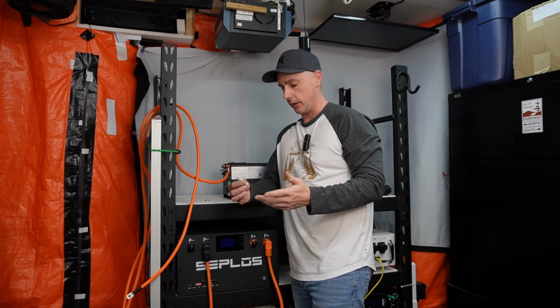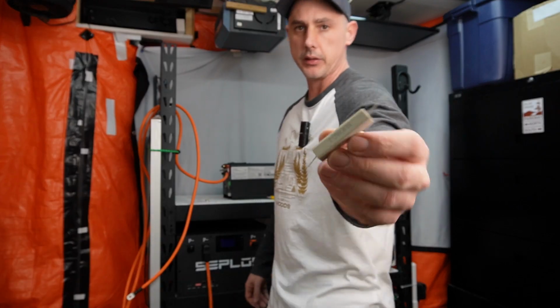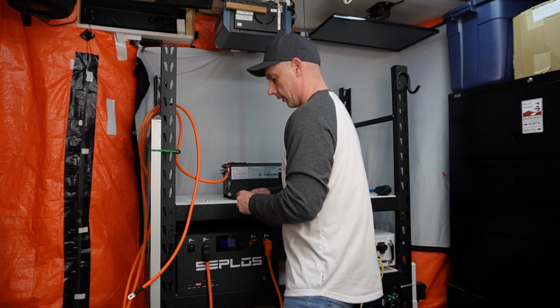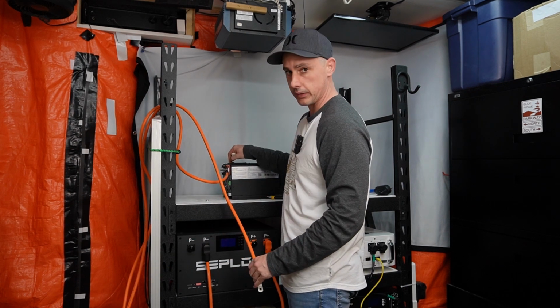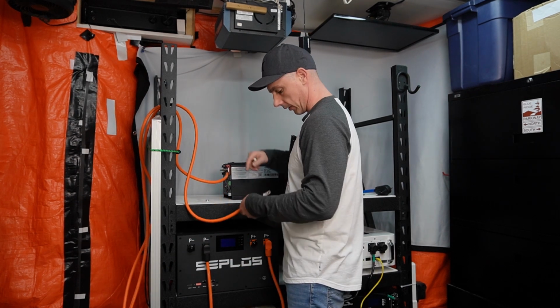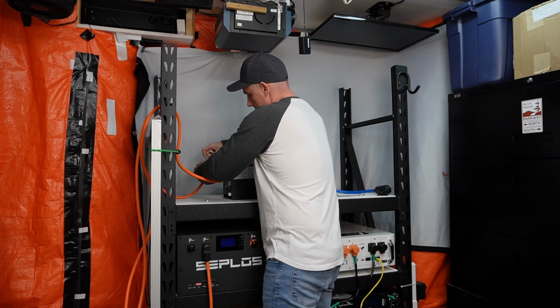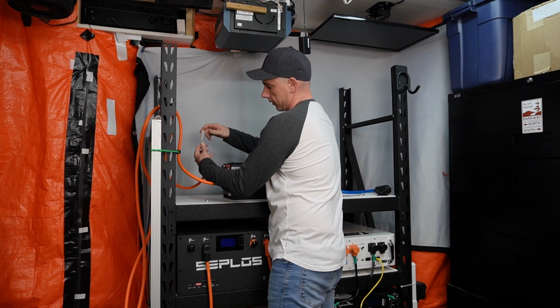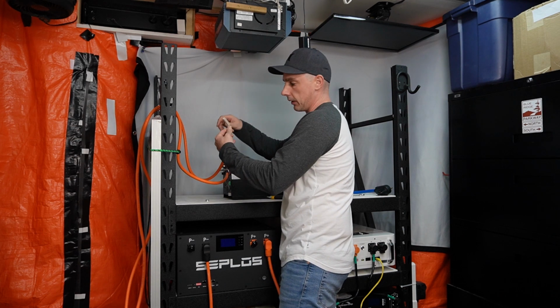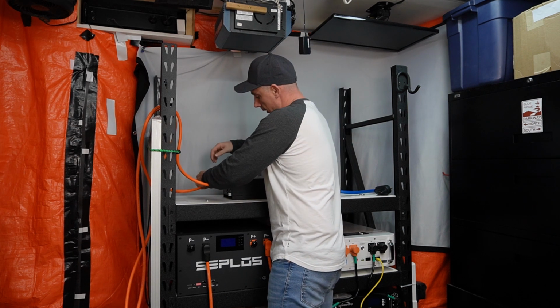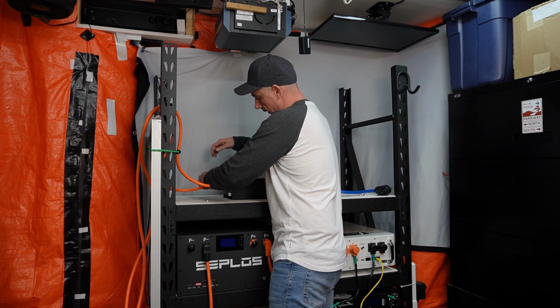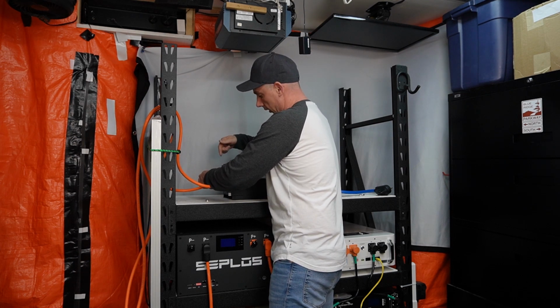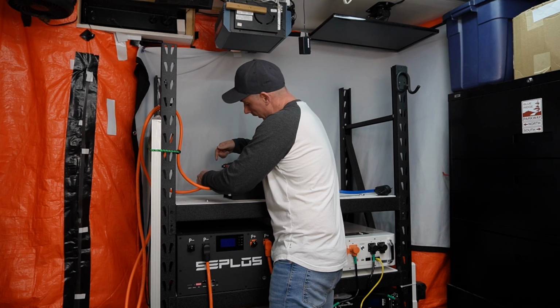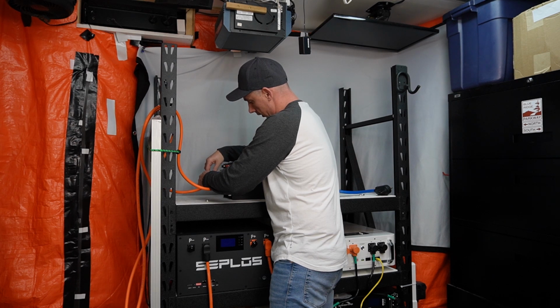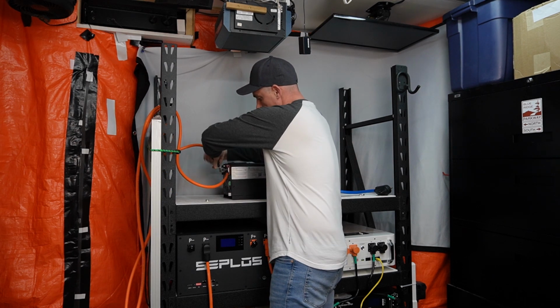Before I make my negative connection, I have a 10-watt resistor, and this will allow current to slowly flow into the inverter, which saves the capacitors inside the unit. I hold it on the positive wire, then touch this extra side to the inverter. We got a small spark - it would have been much larger if I wasn't using this resistor. Once there's enough energy in the capacitor, I'll make the final connection.